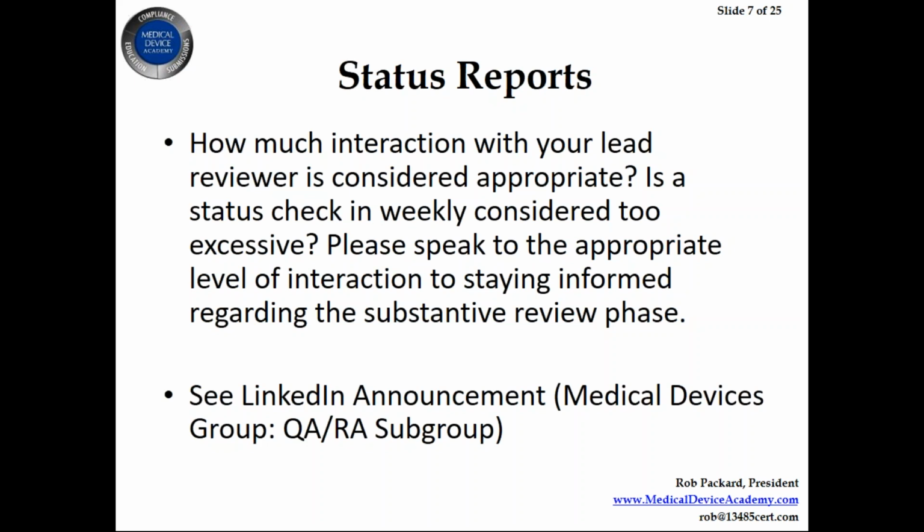They track metrics on each of the different stages of the 510K process, and they report the performance on that in an annual report and talk about gaps in their performance and how they're going to address it, and they're held accountable to Congress. So they don't need every single company that they're doing a 510K for asking that question too. The first step is they're supposed to run your e-copy in their system and upload it to their computer. That's supposed to happen within 7 days. It typically happens the same day. It's rare for it to take more than 24 hours.